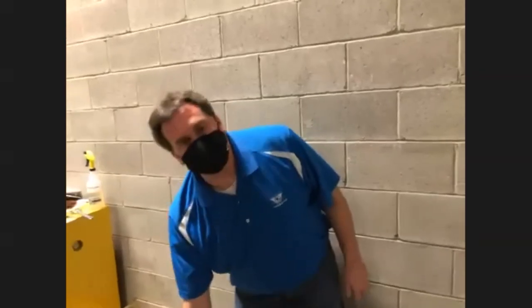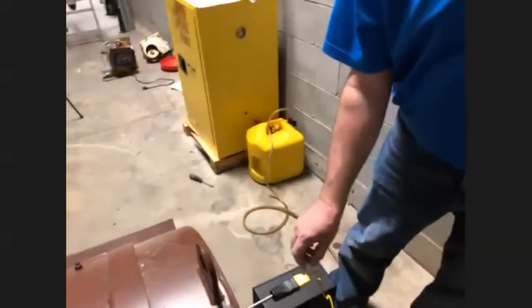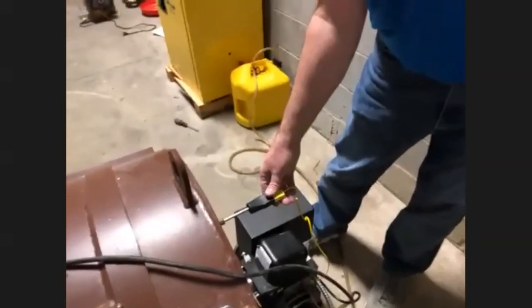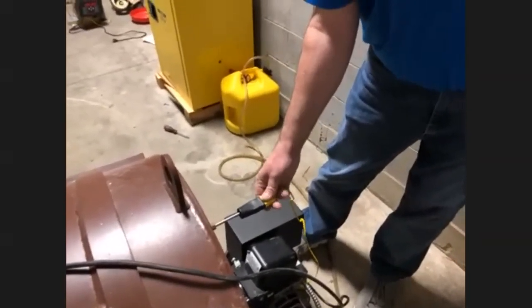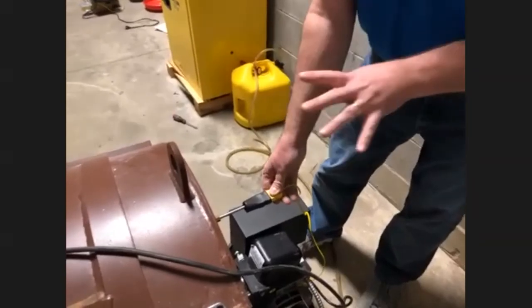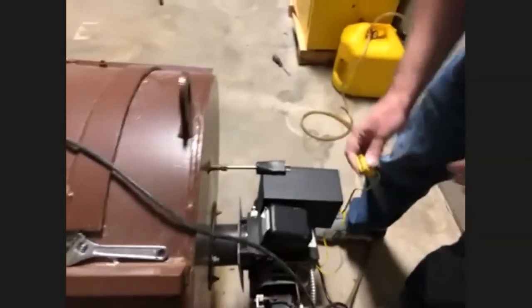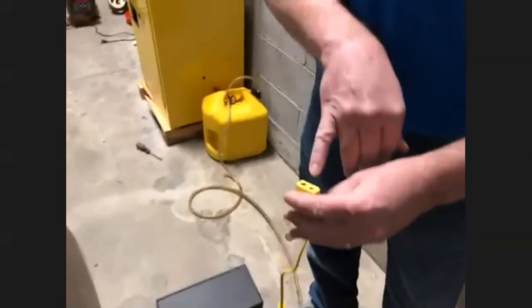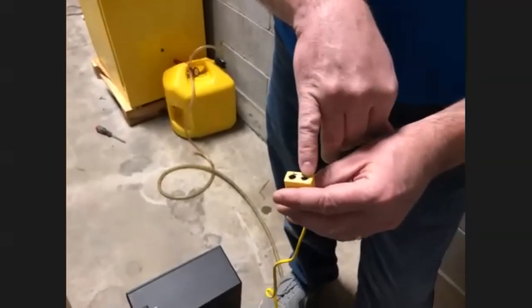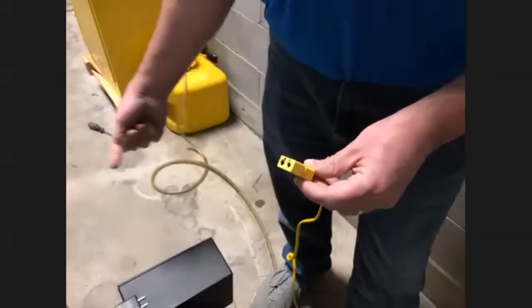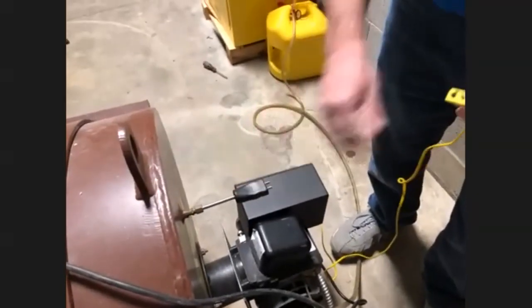With most oil burners, that is most anything you will run across. There may be an issue with the controller. You may get a temp probe failure. The controller will tell you a temp probe failure, where the temp probe itself is not working properly. One way to verify that, whether it be a gas burner or an oil burner, is you can take a wire and make a jumper across these terminals. And if that probe error goes away, then you know your temp probe failed. And you can replace that.